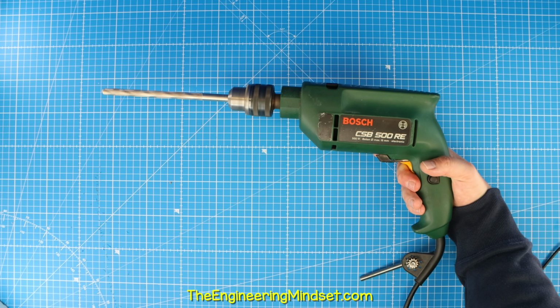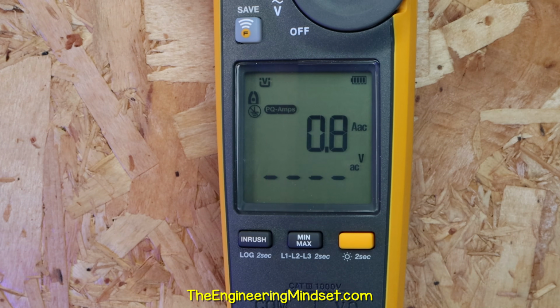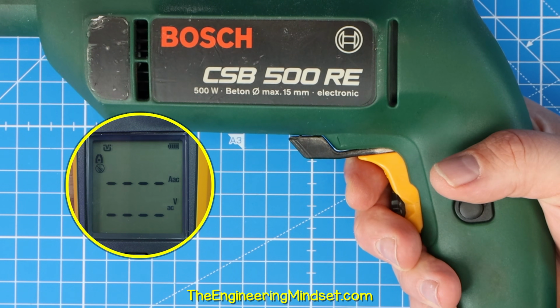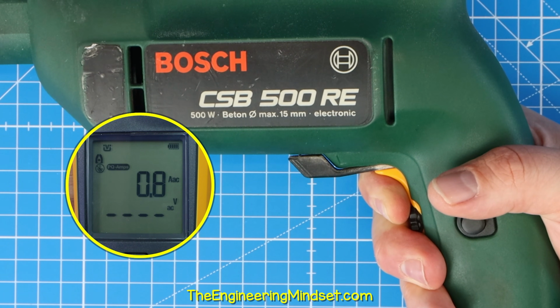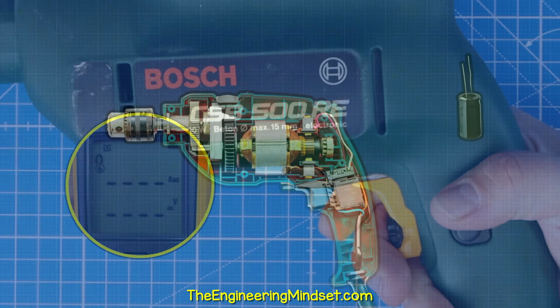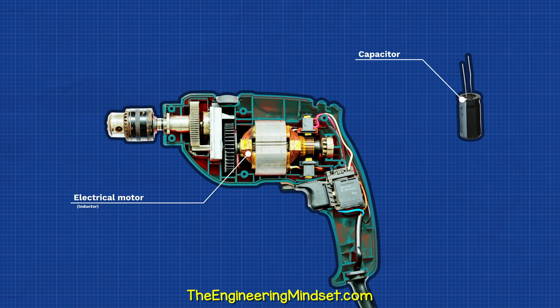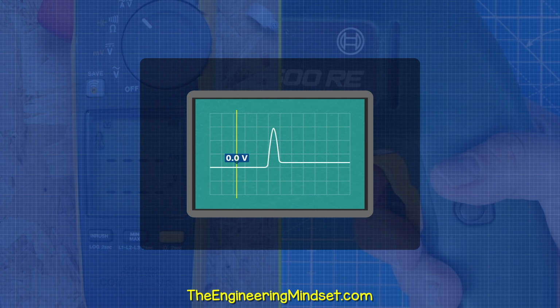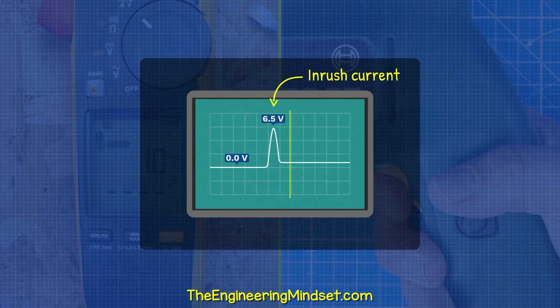When equipment is running, we typically have a fairly constant running current. But when the equipment turns on, we have an inrush current because the capacitors and the inductors inside are all storing energy, and this causes a lot of current to flow. So, for a fraction of a second, we have a large current flowing, and then it will normalize.